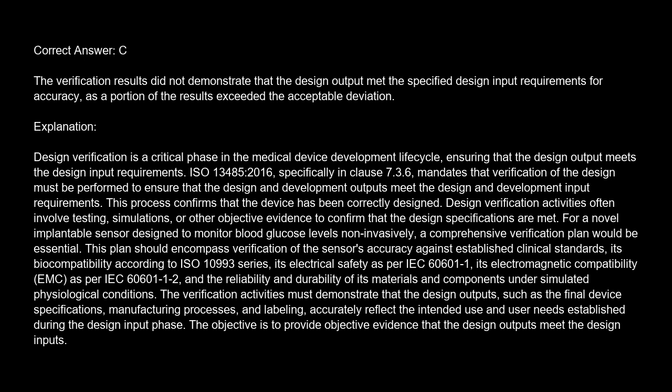The verification activities must demonstrate that the design outputs, such as the final device specifications, manufacturing processes, and labeling, accurately reflect the intended use and user needs established during the design input phase. The objective is to provide objective evidence that the design outputs meet the design inputs.